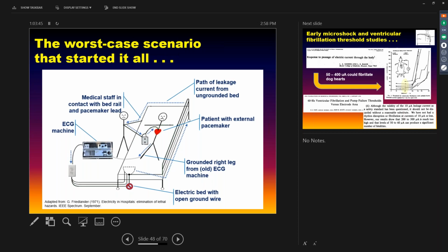You got a bad ground in the bed. Not at all uncommon, beds with a bad ground. So what happens, the leakage current is now available on the frame of the bed, because there's no place for that leakage current to go. So it's floating around, available on these rails of the bed. You have a nurse tending, leaning on the guardrail, making contact with the indwelling cardiac catheter into the heart. That leakage current from the bed, below her threshold of perception, can't even feel it, passes through the nurse into the patient's heart, through to ground - bam - kills the patient.